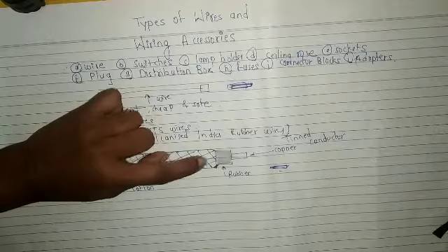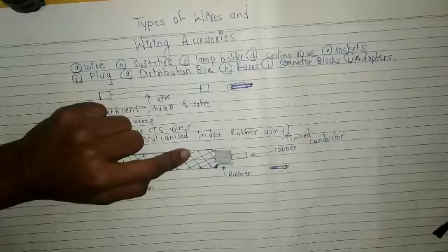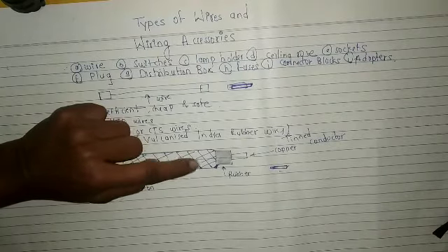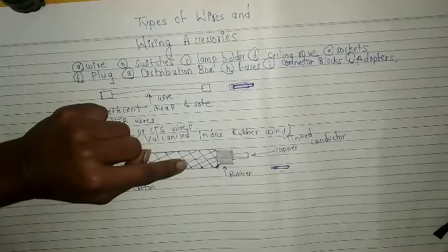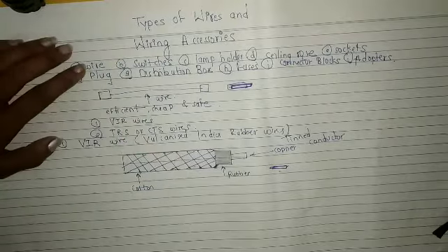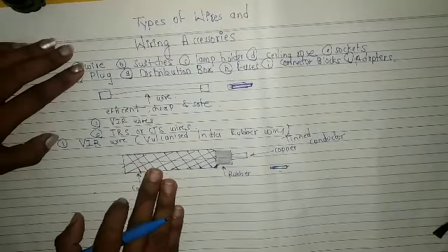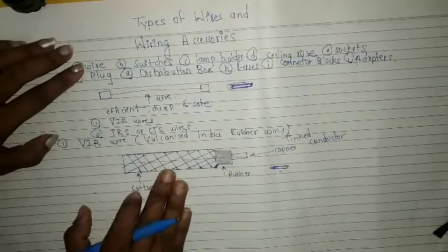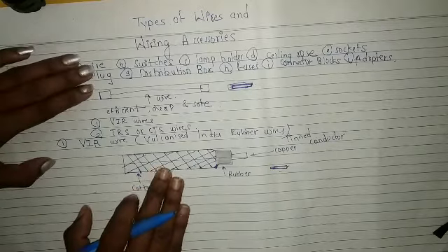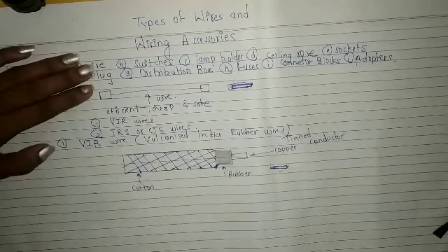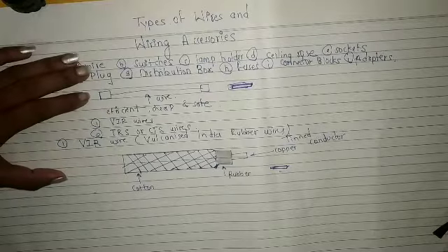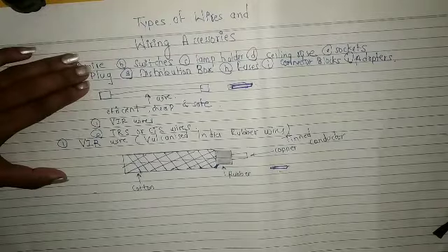So first is our tin conductor, then rubber, and then over this there is a layer of cotton, which is usually saturated with flame retarding and moisture resistance compounding. That means this cotton is saturated so that it will not catch fire, and it is moisture resisting. That means it will also not absorb moisture from the surroundings. Okay, and finally it is finished with wax for cleanliness and helping the pulling action of wire.